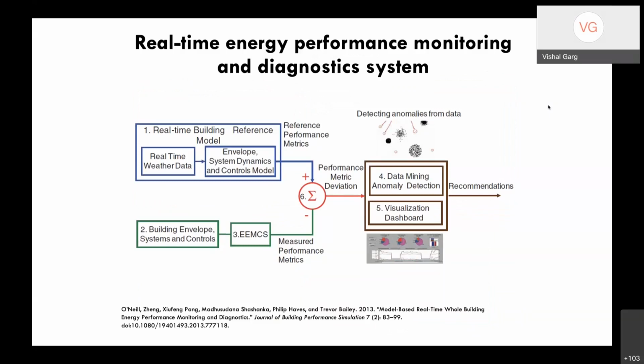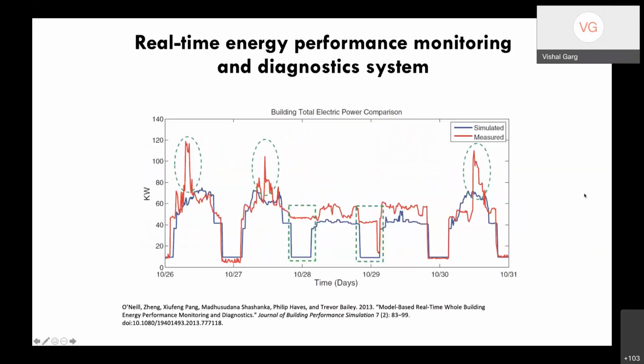With low cost sensing and low cost computing, along with IoT, data mining and AI, it is very much possible nowadays to do this. Instead of just giving all this raw data to a BMS person, who then has to make sense of it and figure out where the fault is -- and many times he won't recognize it -- the machine can tell that this is a fault. Here the machine compares the measured values with simulated values and says, the simulation gives this blue line, so why is the measurement showing this much kilowatt? There's a fault -- so the machine is telling us there's a fault here.